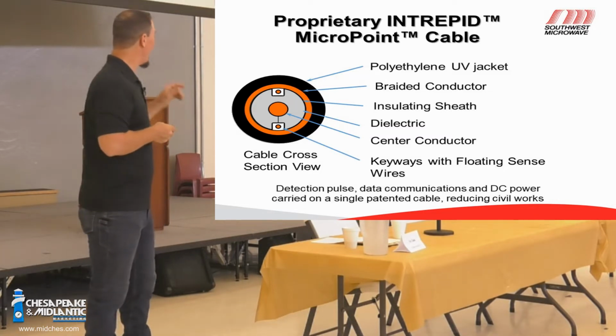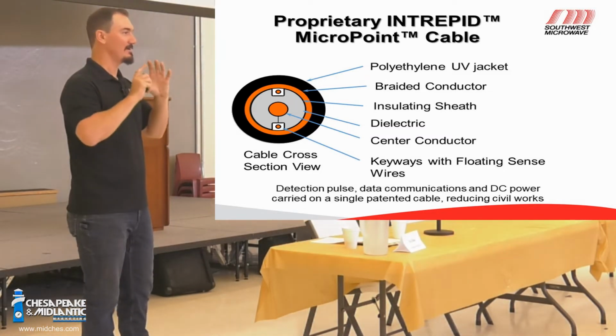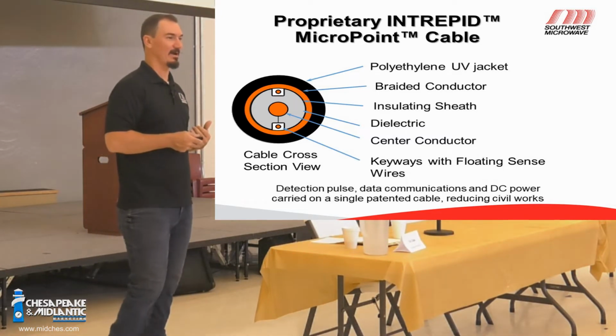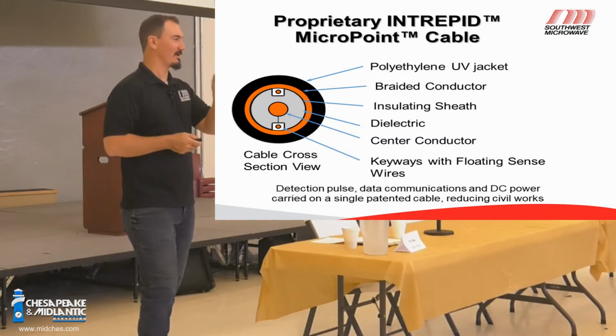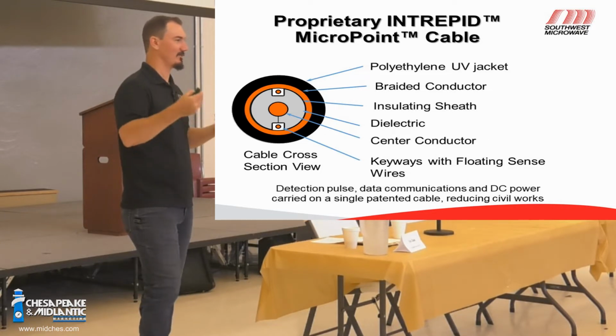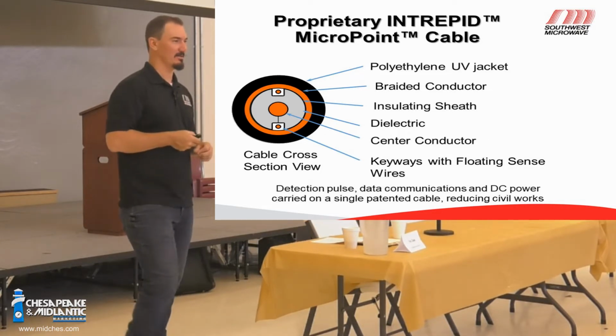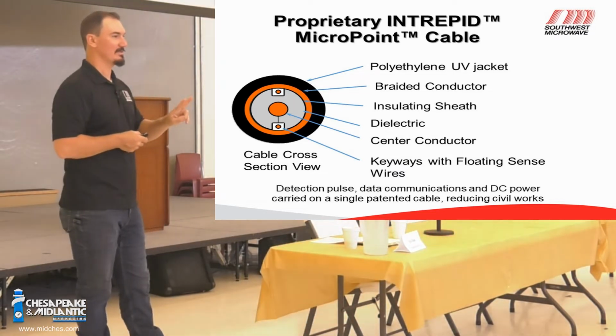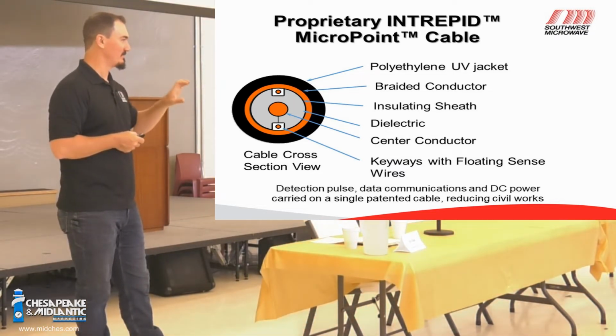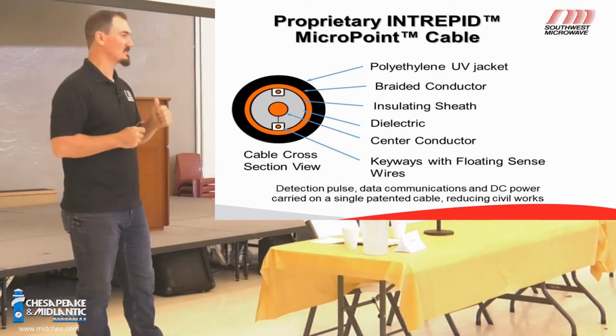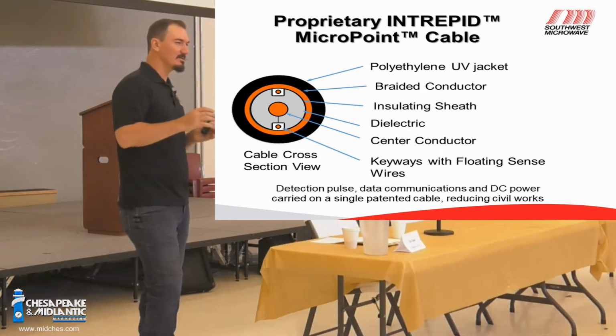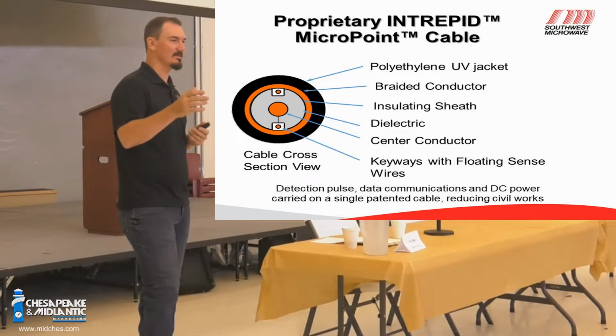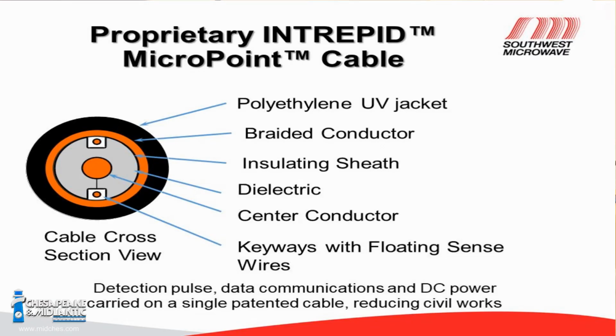Okay? So outside of that shield, we have a braid, and the braid is what provides your floating ground. So you'll notice that there's not a bunch of ground rods on the fence system. Each processor is not grounded around the perimeter. We only ground the fence-mounted system at 2 locations, and that's where you have power. So where we have the JB70 surge protector come in, that's where we're providing a ground. Once you get about 60 or 70 feet or so away from that processor, that braid provides the ground potential. And by using a floating ground potential on the sensor, we electrically isolate it from the fence structure itself.